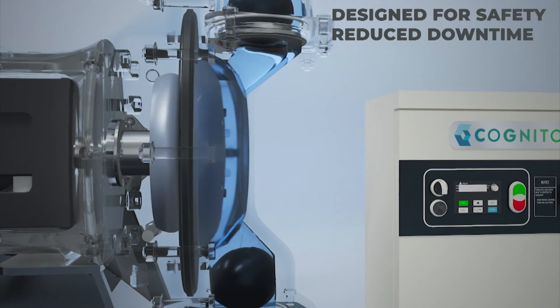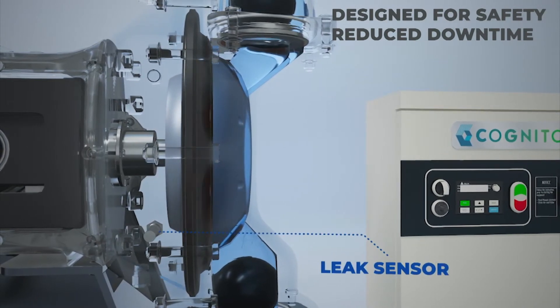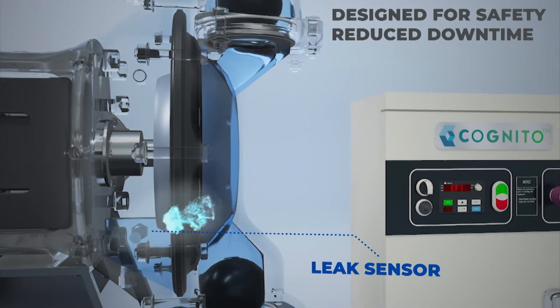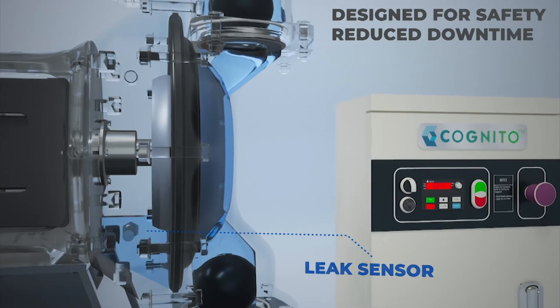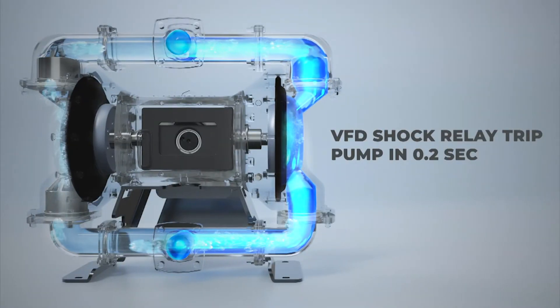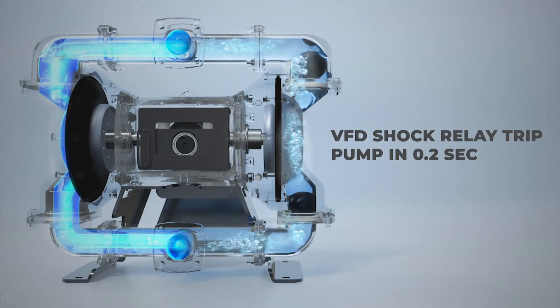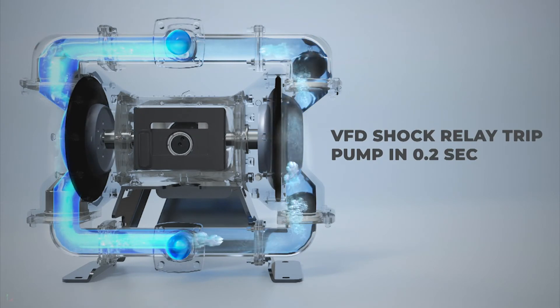The leak detector sensors detect even a small leak from the diaphragm and trip the pump to avoid leakage of the process fluid and eliminate hazardous conditions. Pump automation is designed in such a way that it can protect itself in choke condition or deadhead application.